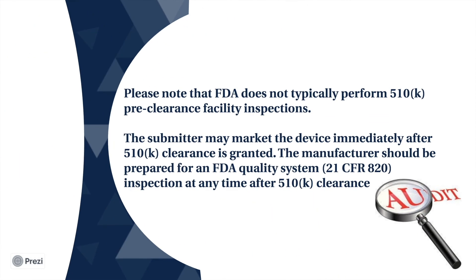Please note that FDA does not typically perform a 510(k) pre-clearance facility inspection. The submitter may market the device immediately after 510(k) clearance is granted. However, the manufacturer should be prepared for an FDA quality audit at any time after 510(k) clearance.